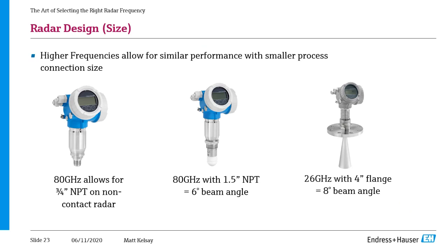So when we look at radar design, the biggest thing that's influenced by the frequency is the physical size of the unit. So again, higher frequencies are going to allow for very similar performance, but with smaller process connections. So looking left to right, an 80 gigahertz radar for the first time allows us to get down to a 3/4 inch NPT non-contacting radar device. Previously, 1.5 inch was as small as we could go. So this is great, especially in retrofit type applications where maybe you had a capacitance probe or a guided radar installed before. All you have available is a 3/4 inch NPT. Now, if the application allows, we can put a non-contact radar in there as well.